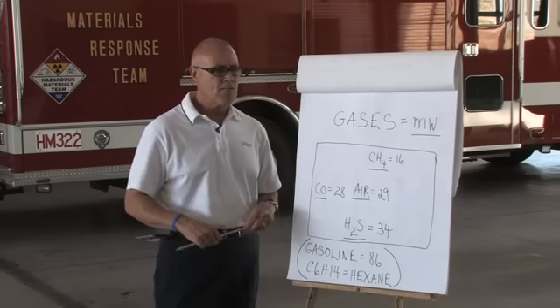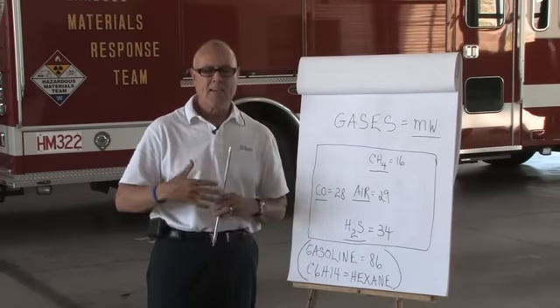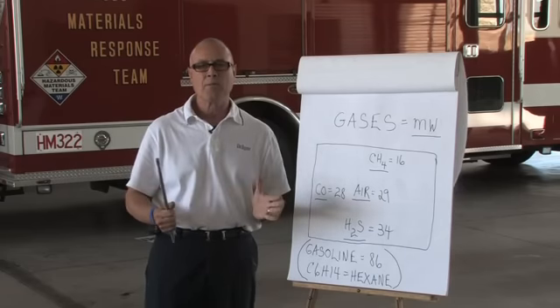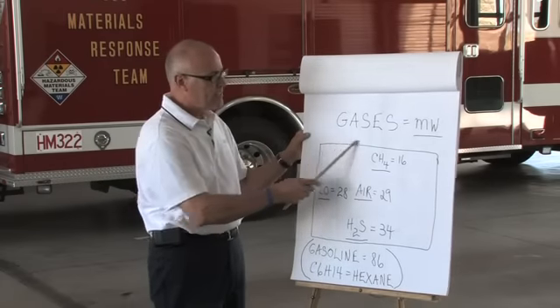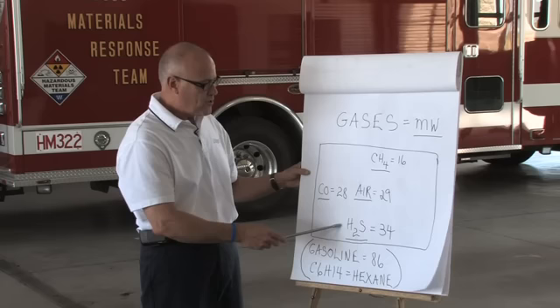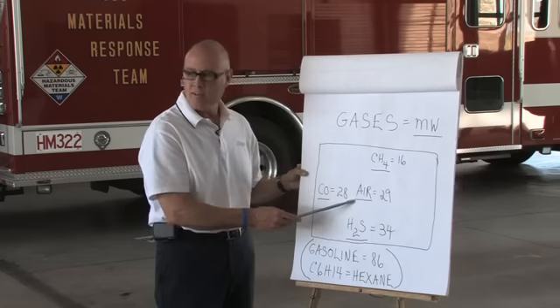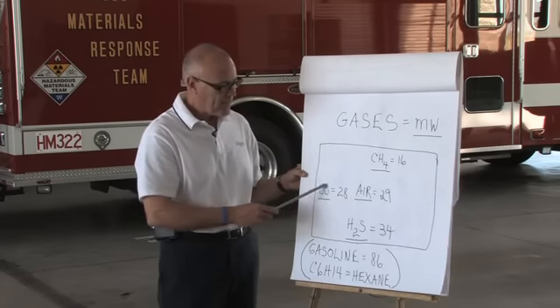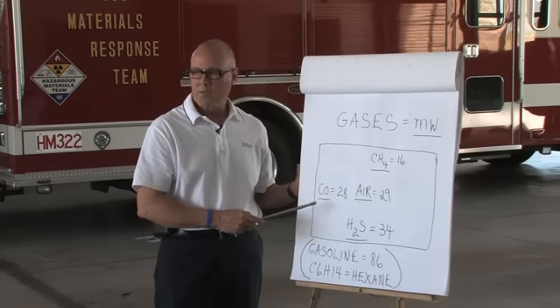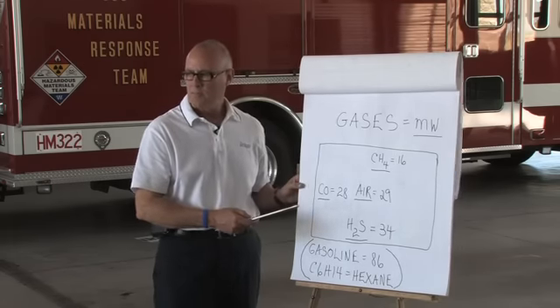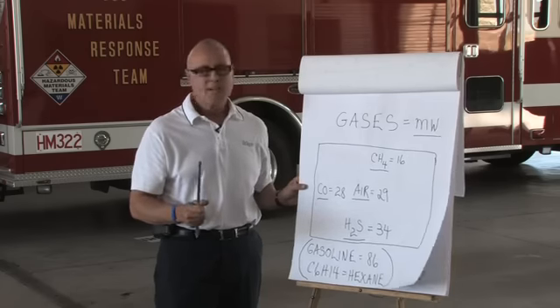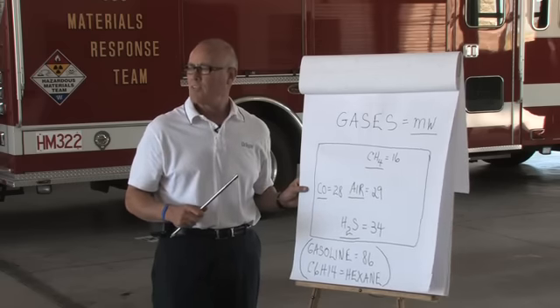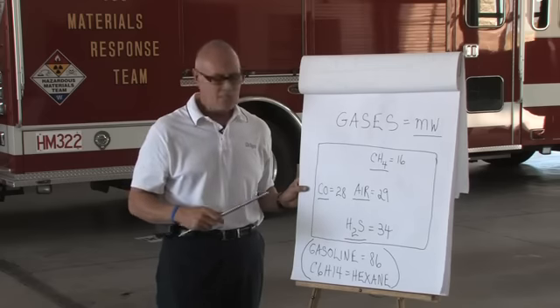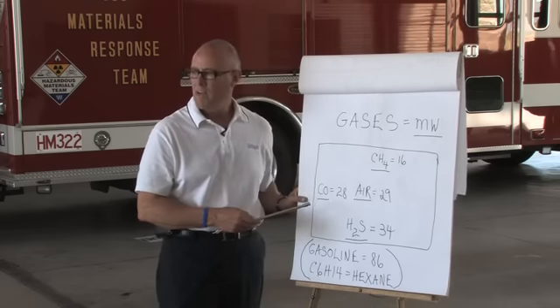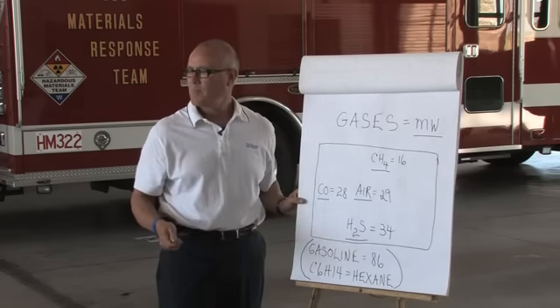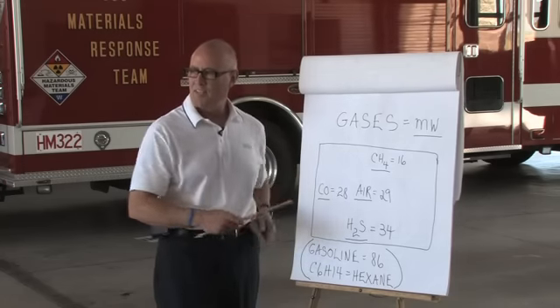Well, okay, the question is, how far can the instrument detect ahead of itself as you're walking into a structure without a pump? And in this given scenario, when you walk in the door, you're going to be picking up the air concentration in that space. If carbon monoxide is present, you're going to pretty much pick it up pretty quick. There's a term called Fick's law of diffusion, which is a passive rate. Consider it the rate of gas traveling through the instrument without having a pump on, if you can think of it that way. In Fick's law of diffusion, your fixed rate of flow is about 500 cc's. Without a pump. But the gas has to be present for the instrument to see it.